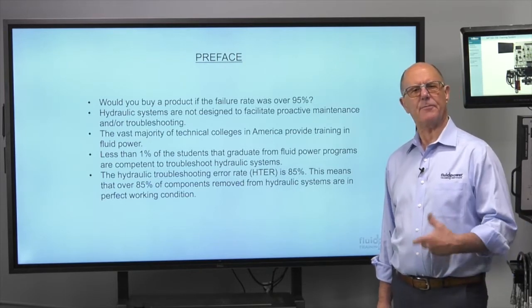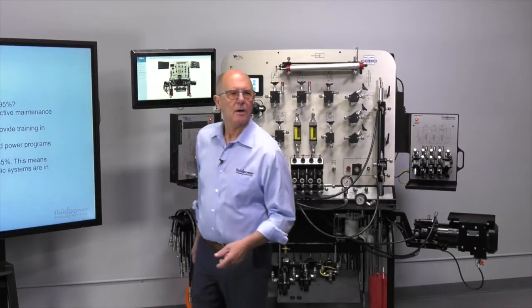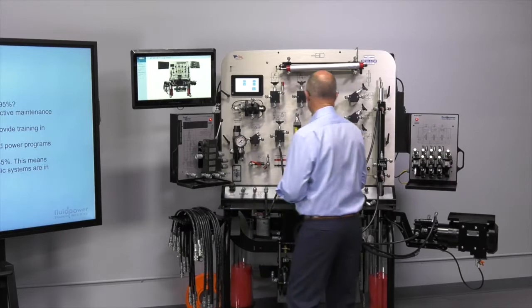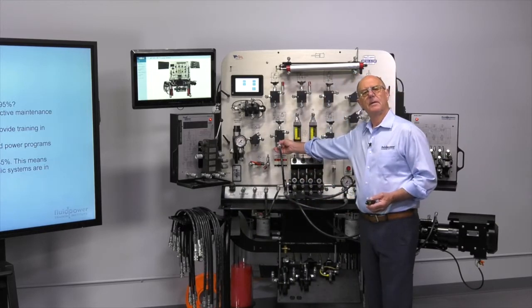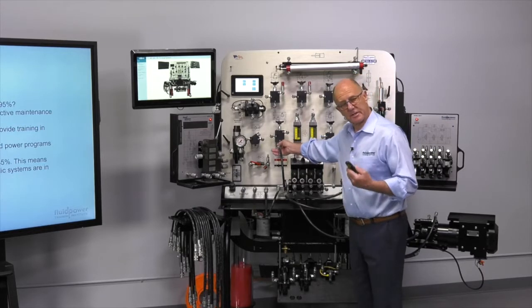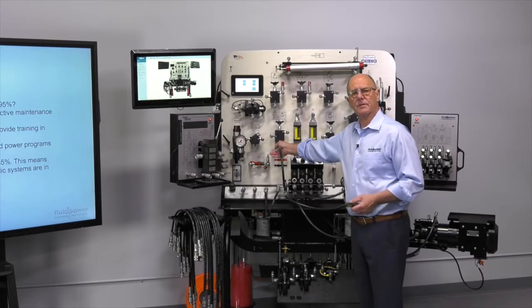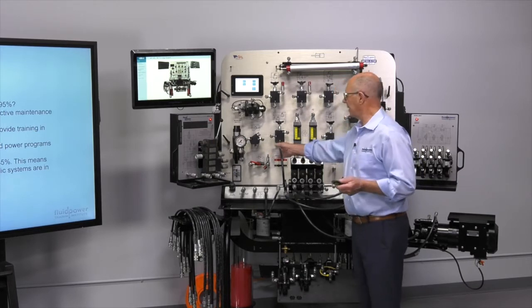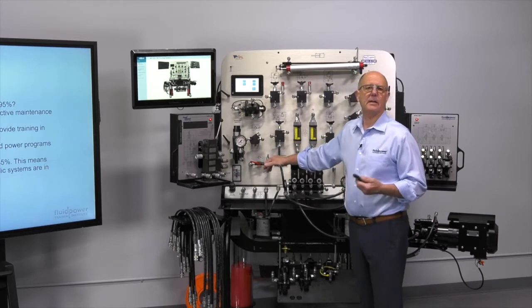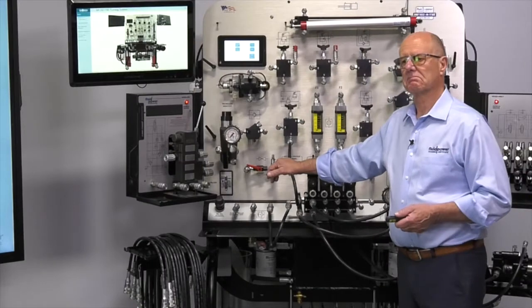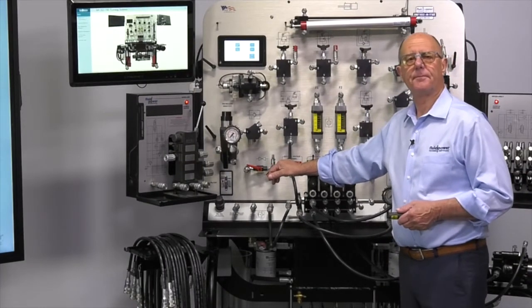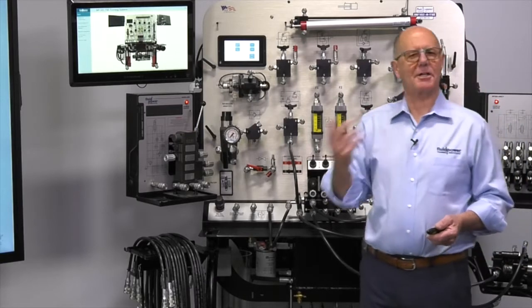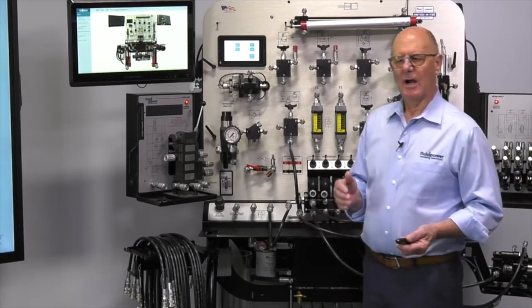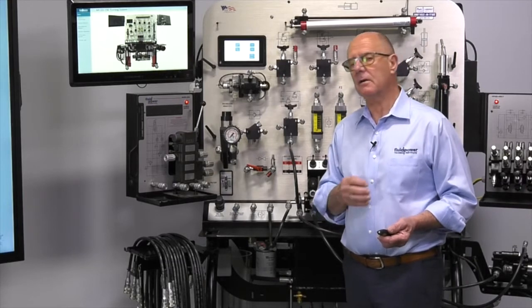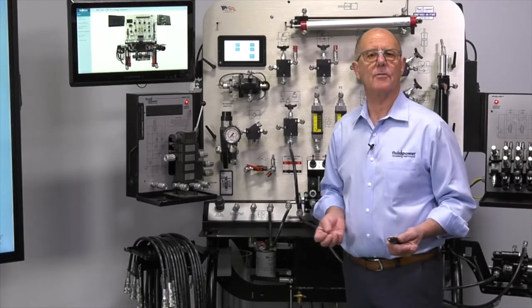So let's see if we can solve this problem. When I go up to a component, let's say, for example, a pressure relief valve over here, and I'm going to troubleshoot it, I'm going to demonstrate to my students how to troubleshoot it. I ask them before I embark on the procedure, have you ever had reason to believe that a relief valve was defective, leaking internally? And they said, yes. I said, what did you do? They said, replaced it. Folks, that's 97% of the answer. So I give it a margin of error of 15% only because some of the students don't like to vocalize.